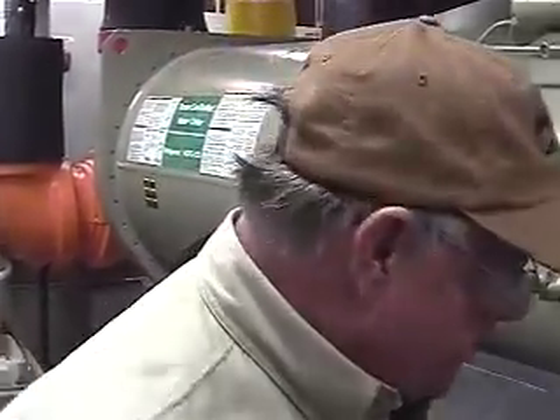Okay, out here in the chiller room, remember when I talked about the orifice plate going into the evaporator? That's situated right down there. It goes into the evaporator right there, right down at the bottom of the chiller. That channel iron that I was telling you about is a distributor plate that goes all the way the length of the bottom of the evaporator.